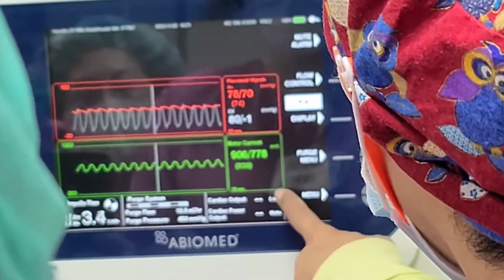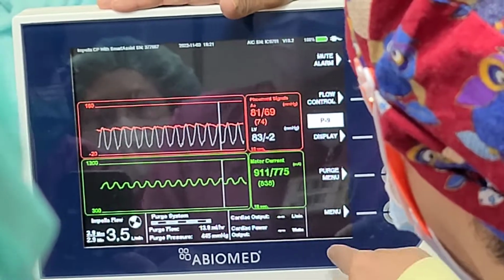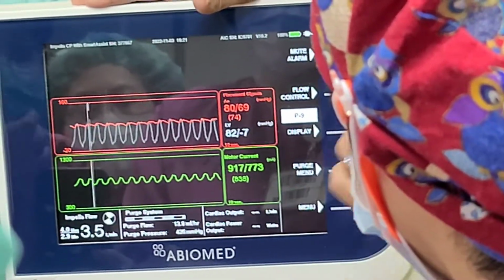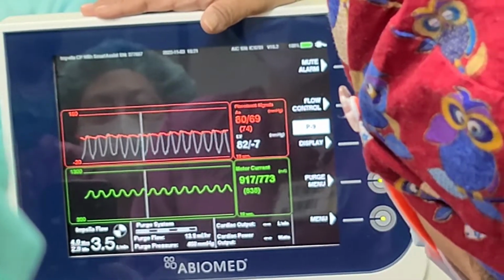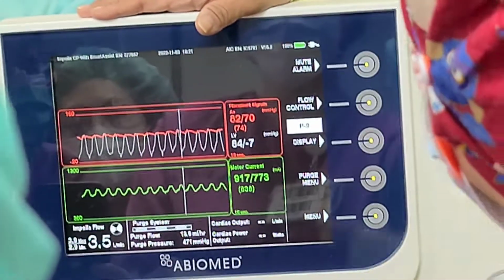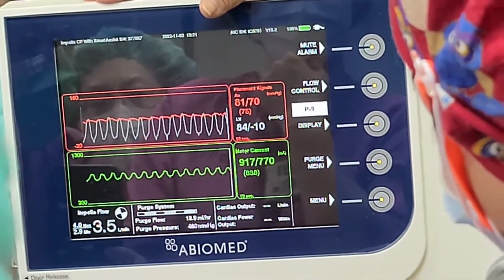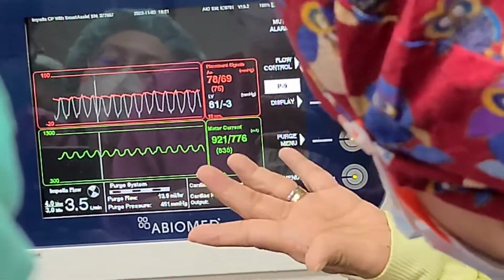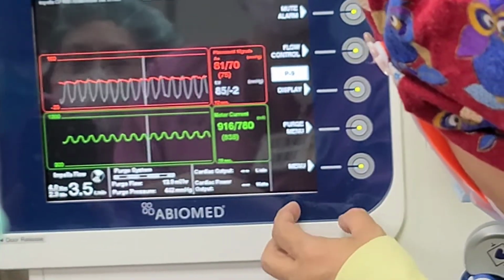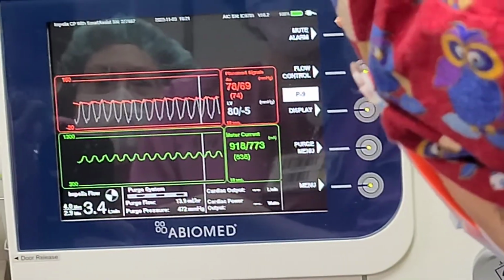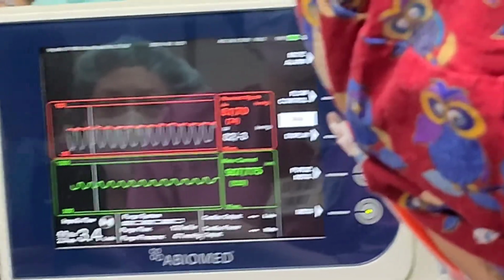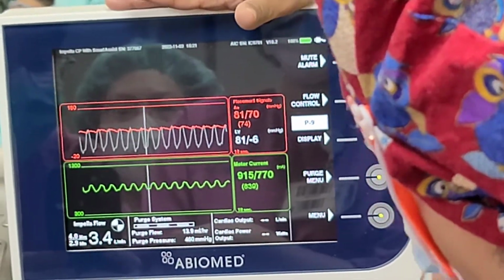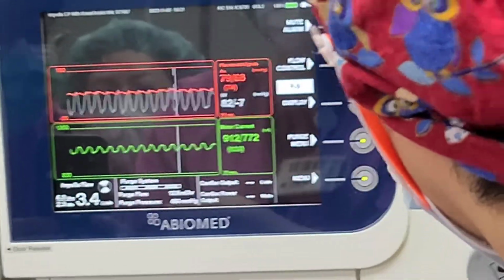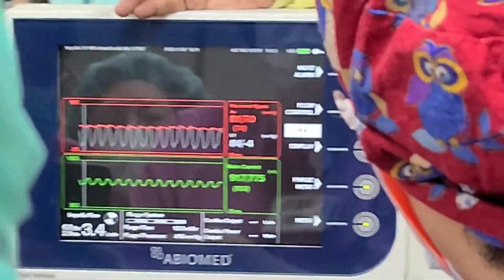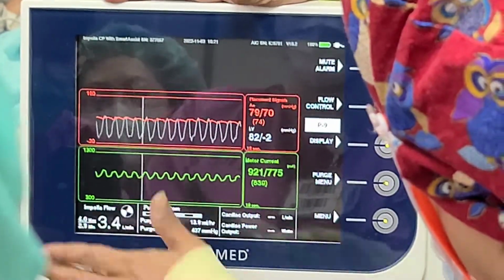Then the cardiac output - if you enter in the cardiac output, remember I said if you go to menu you can enter it, the machine will calculate a cardiac power output for you. You don't even need to do that, it's amazing. But you must remember, this value that you put in here only lasts for 8 hours. At 7 hours, you get a reminder to put in a new cardiac output. Again, you don't need to remember, it will remind you. Now, is everybody okay here?